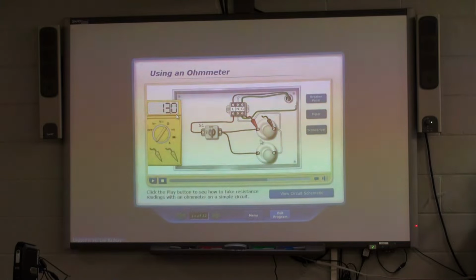I'm proud of you. If we measure across a single bulb, just connected, we get 26 ohms. Then we returned it and measured across it again, and we suddenly go from reading 26 ohms, which is just the resistance of a single bulb, to the parallel resistance of this other bulb. If we have 26 ohms and 26 ohms in parallel, remember, if they're both the equal value, we can divide it exactly in half, or we could do product over sum. We could do 26 times 26 over 26 plus 26, and we would arrive at 13 either way. This lower resistance is due to the parallel path through the second light bulb. This demonstration shows that you need to isolate the component before testing to avoid misleading resistance readings.